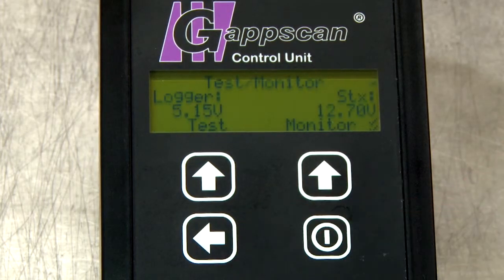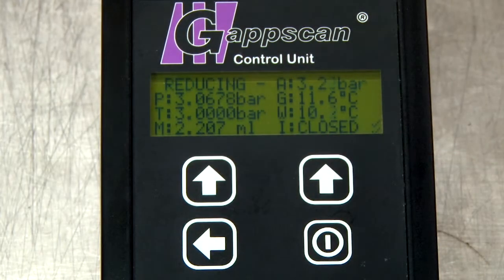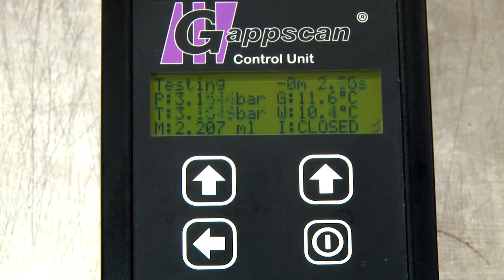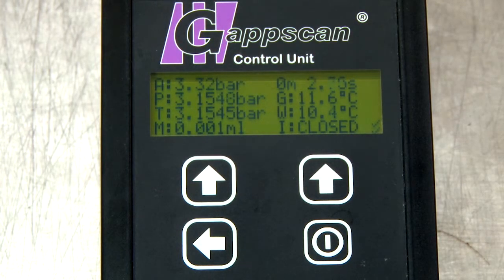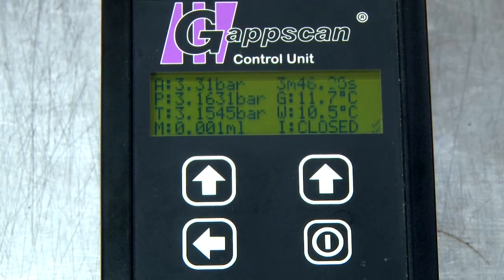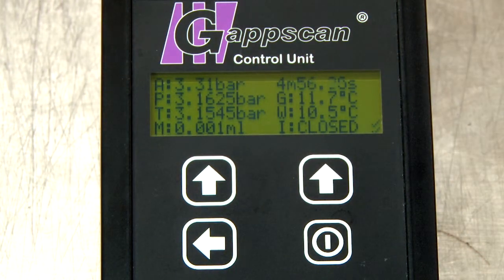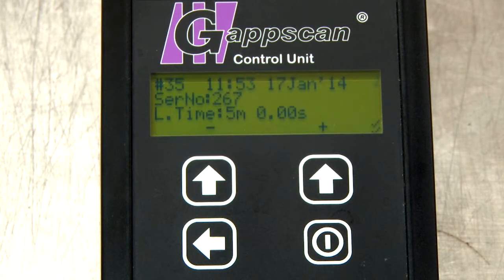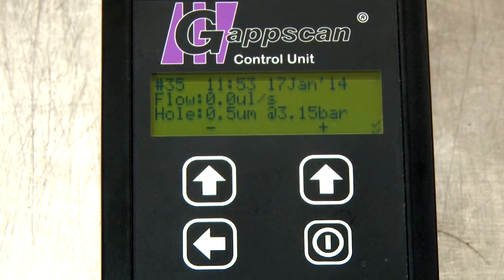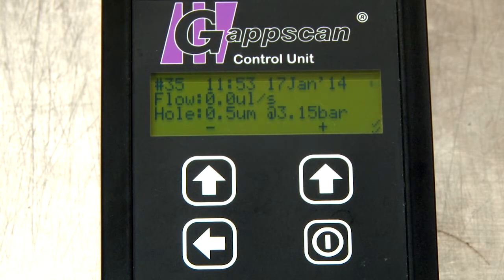Press the return key, then select Test from the menu. When Test is selected, an automatic sequence begins. The test time will be seen incrementing in real time until it reaches 5 minutes. When complete, the monitor will switch to the individual test screen shown here. Press the I/O key to display the test data. A hole size of less than 5 microns will determine that the Gappscan system is not leaking.